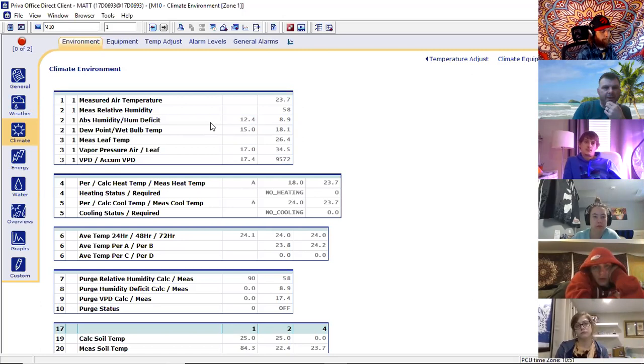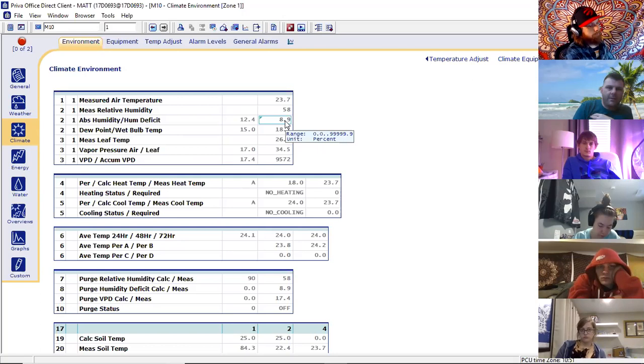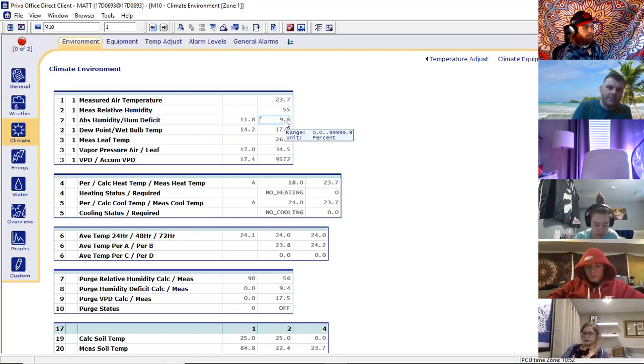There's something called psychrometric graphs — I'll get into that maybe next week or the week after — showing how all of these are calculated from just two sensors. The psychrometric graph or Mollier diagram will tell you specifically what's going on in the air compared to the temperature and the amount of moisture. It gives you absolute humidity — the direct measurement of water actually in the air, like 12.4 grams per cubic meter. The humidity deficit is how much moisture can still fit into the air at a given temperature. Think of it as a glass: the warmer the air, the bigger the glass.